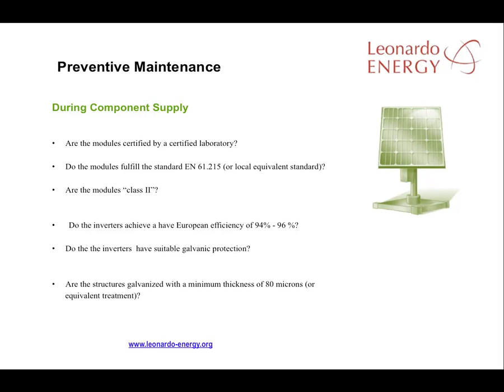In choosing components, special care should be taken over the main and most expensive elements in the solar plant: the modules and inverters. For the modules, there are three issues to consider. Are the modules properly approved by a certified laboratory? Do they meet local and national standards? If the plant is in Europe, the relevant standard would normally be EN 61.215. Third, are the modules Class 2?